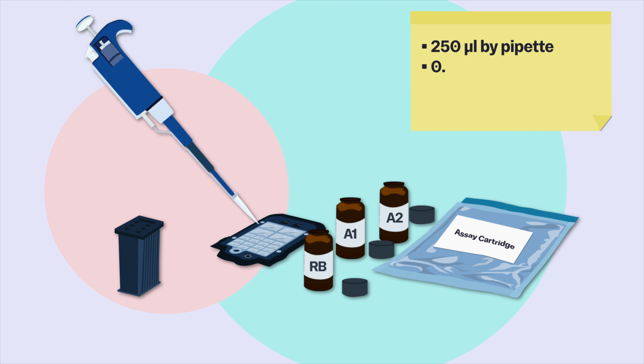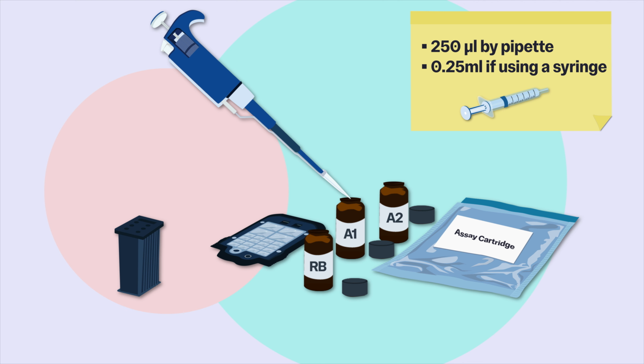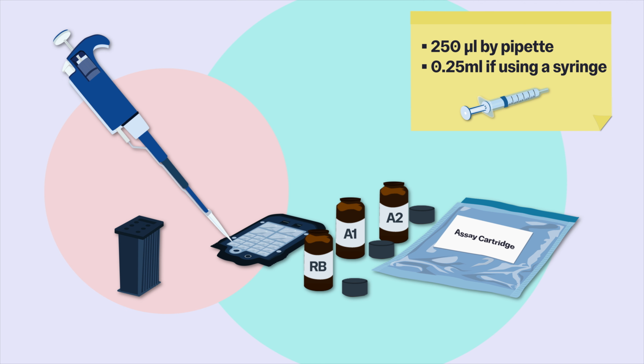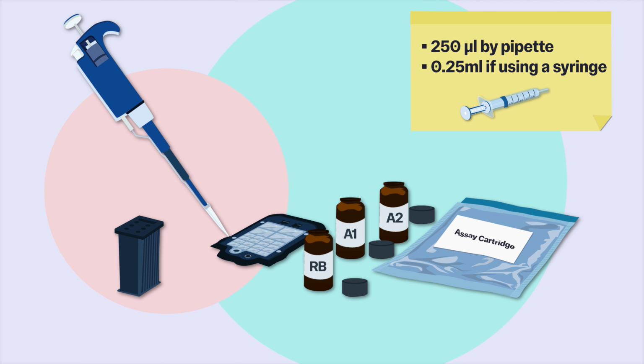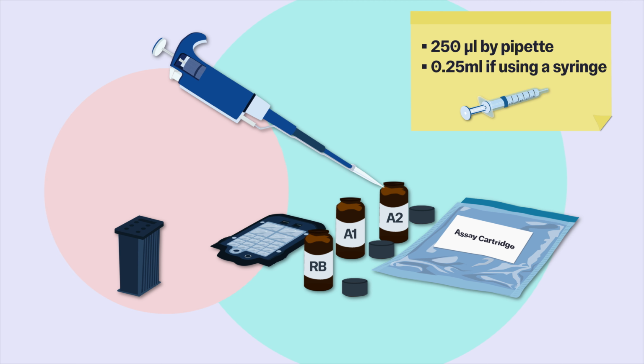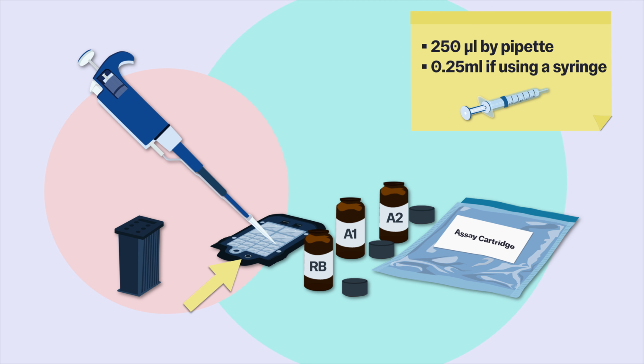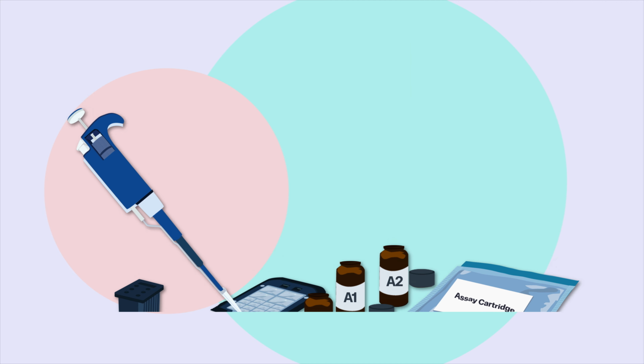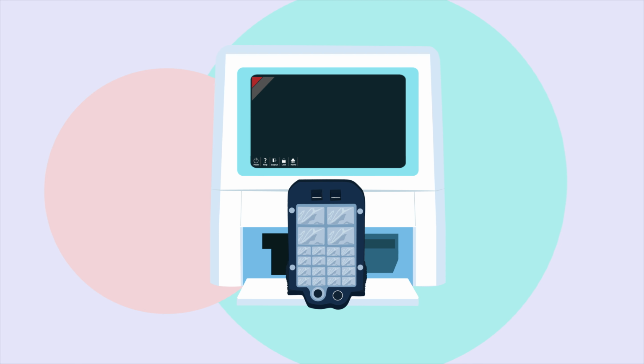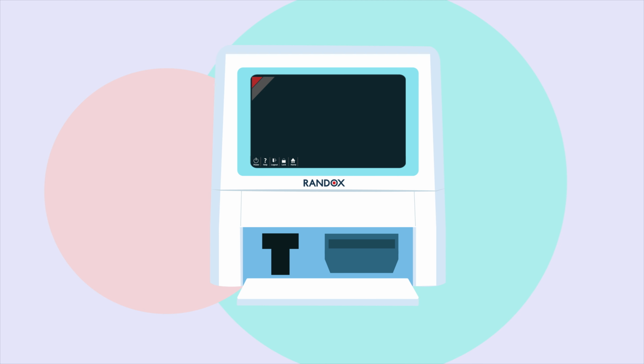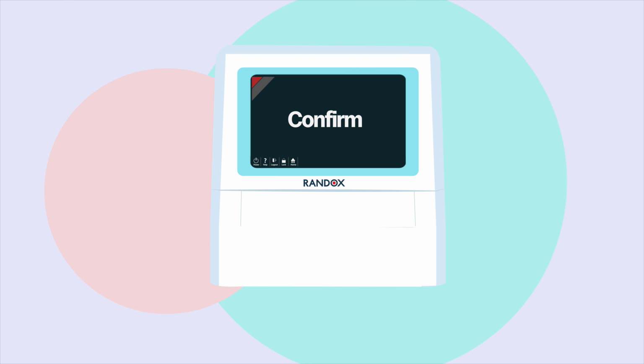Transfer 250 microliters of reconstituted Adjuster 1 to the left well. Use a fresh pipette tip or syringe to transfer 250 microliters of reconstituted Adjuster 2 to the right well. Load the assay cartridge into the right-hand drawer and the tip cartridge into the left-hand drawer of the device. Push both drawers into place gently until you hear a click and close the door. Select Confirm. If the cartridges have been loaded correctly, you will then be able to select Run Test.